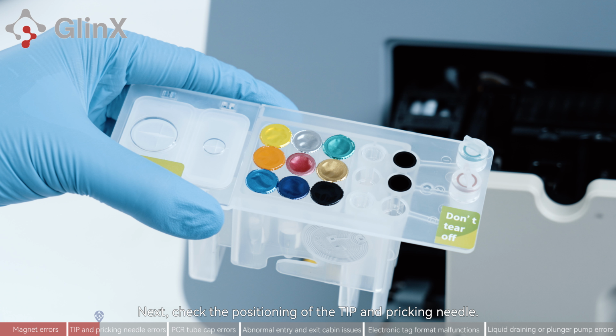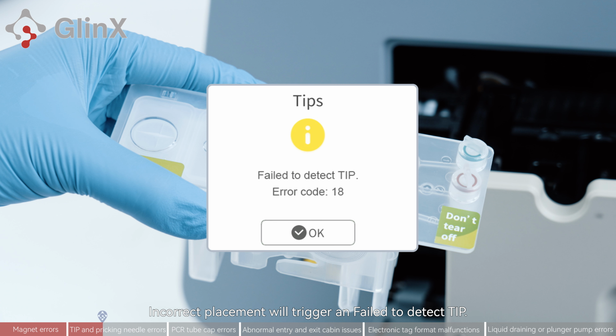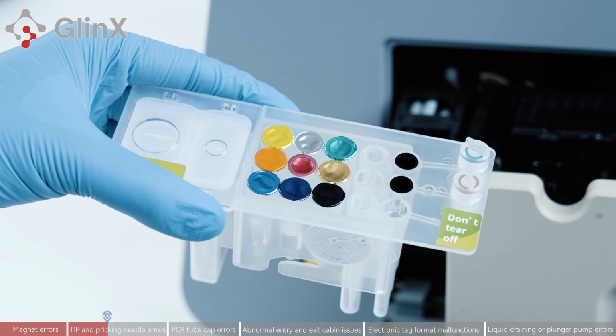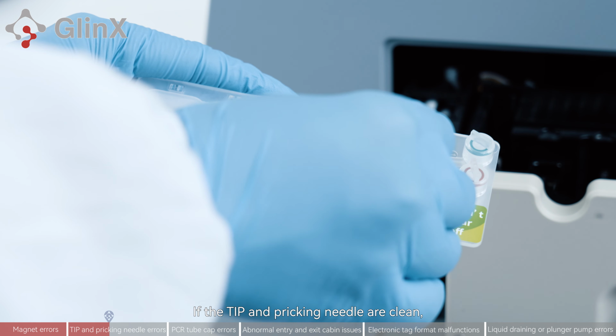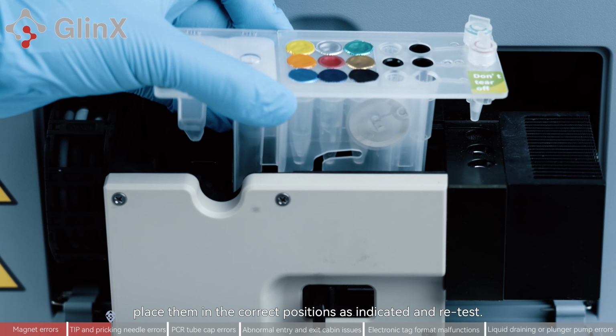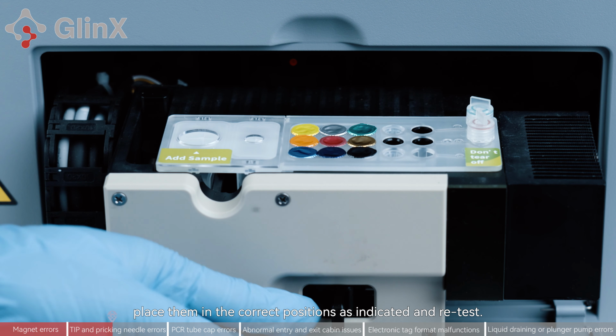Next, check the positioning of the TIP and breaking needle. Incorrect placement will trigger a failed to detect TIP, error code 18, on the instrument display. If the TIP and breaking needle are clean, place them in the correct positions as indicated and retest.